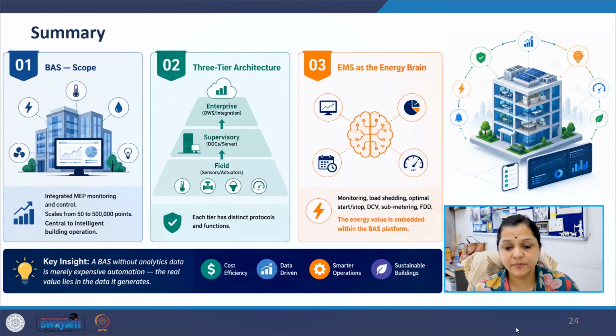At the time of summarizing this discussion, we can say that the building automation system provides integrated monitoring and control for mechanical, electrical, and plumbing systems within intelligent buildings. The BAS structure operates through three main levels: first is field devices, then supervisory systems, and enterprise integration. Energy management systems embedded within building automation platforms support monitoring, load shedding, demand controlled ventilation, sub-metering, fault detection, and optimization strategies. The key insight presented throughout the session is that the true value of BAS lies not only in automation but in the operational intelligence generated through data analysis.